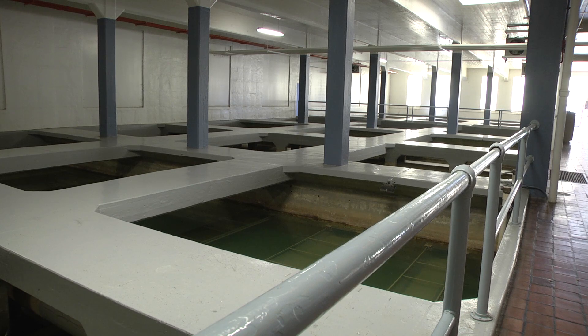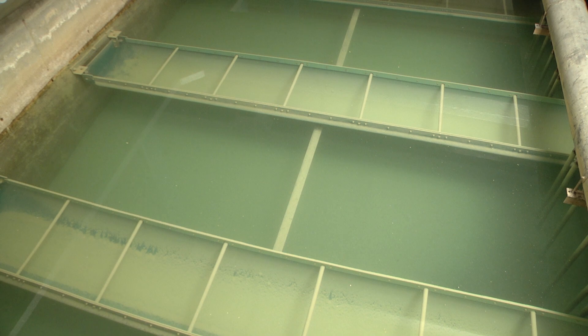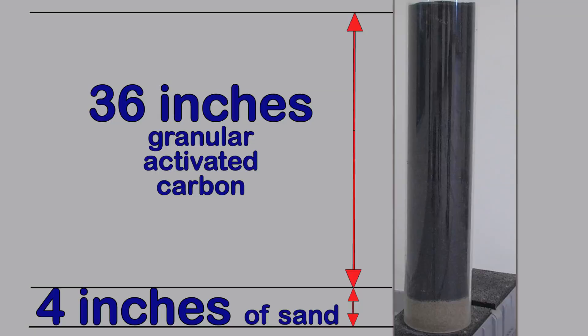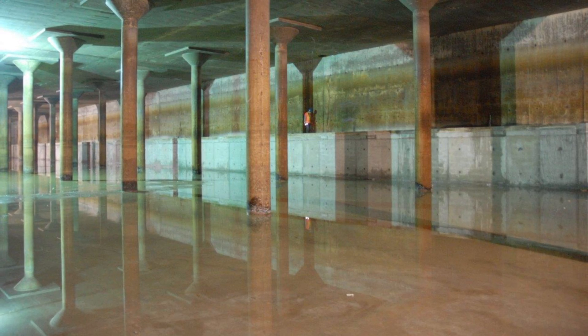After reducing the pH level, more settling occurs as the water moves through the secondary settling basins and onto the filters. Here, the water filters down through 36 inches of granular activated carbon and 4 inches of sand. The granular activated carbon removes small particles and the molecules that cause taste and odor issues. The filtered water is collected and sent to the underground finished water reservoir.